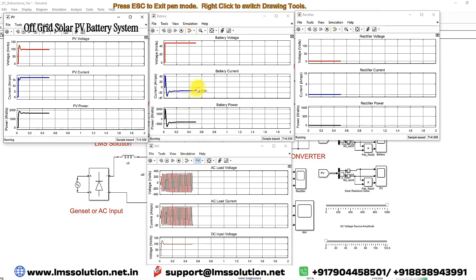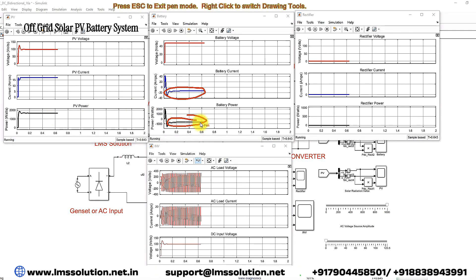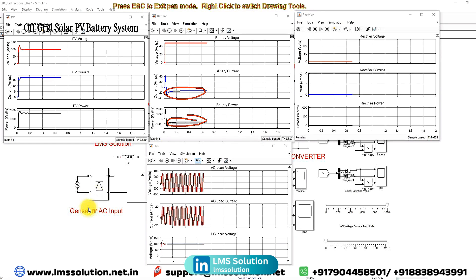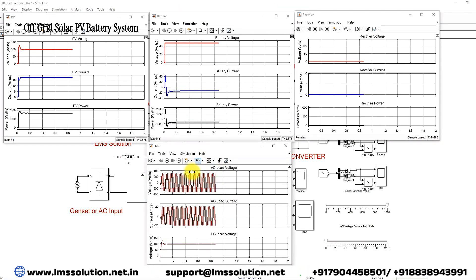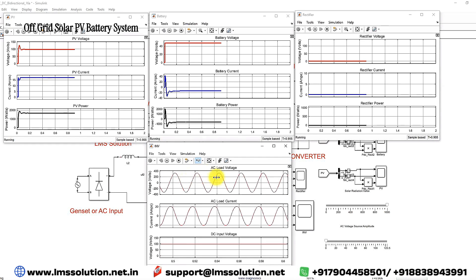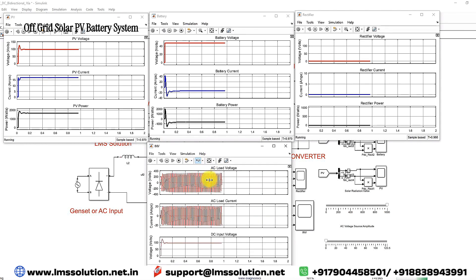The battery current is negative, which means the solar is generating excess power — the battery is in charging mode. We are not using the backup generator or AC input, so the generator voltage and power are zero. The AC load is getting a sinusoidal voltage, and the AC load is continuously getting power from the PV. The excess power is going to charge the battery.